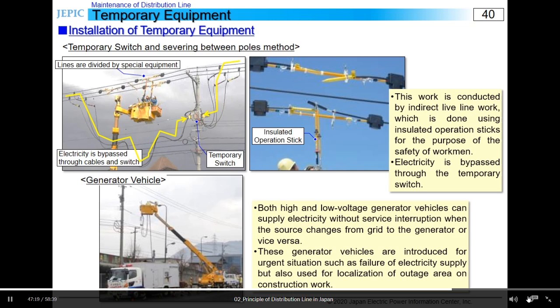The upper right one shows how to reconnect conductors in this method. This work is conducted by indirect live line work, which is done by using an insulated operation stick for the safety of workmen. The lower photo shows a high voltage generator vehicle being installed. There are high voltage and low voltage types of generator vehicle, both of which can transfer the load from the commercial power source to the generator without power outage. These generator vehicles were introduced for emergency supply, but they are also used to localize the area of power outage when construction work is being done.